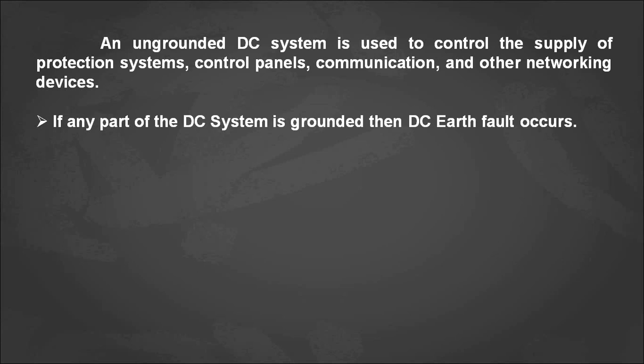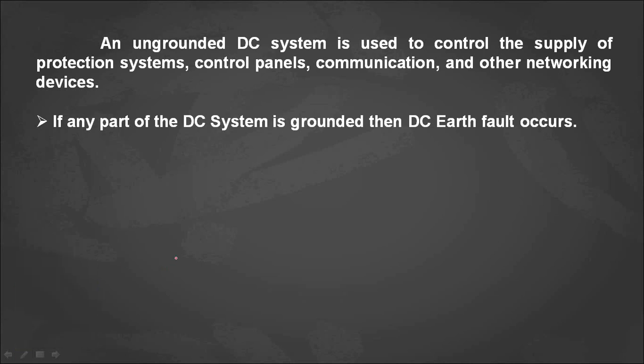An ungrounded DC system is used to control the supply of protection systems, control panels, communication, and other networking devices. If any part of this system is grounded, then we say a DC fault has occurred. Generally, a battery bank is used as emergency or backup supply for an industry or power generating station. The battery bank is a combination of batteries depending upon the voltage required. Generally 220 volts DC is used in many industries, connected to two bus bars — one positive bus bar and one negative bus bar.